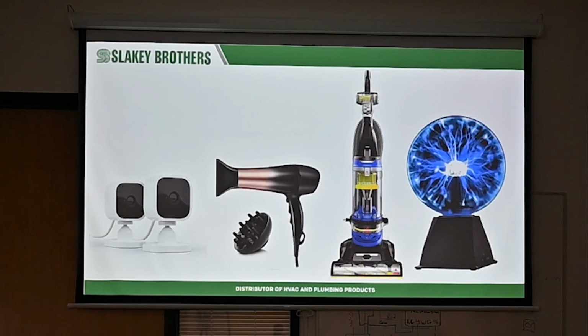One of my installers, just after going back time and time again, he's like, "Hey Juan, you think this?" I'm like, "Let's try it," because it was like a consistent, once a week or a couple times a week, communication fault. All this stuff here in outlet, the electrical line. So if here's the electrical, and on the other side of the wall is the thermostat, and if that electrical runs pretty close to that thermostat, and as the vacuum is running or a blow dryer is running in the room, that's an interference, which is why we got to be careful when we run low voltage next to high voltage.